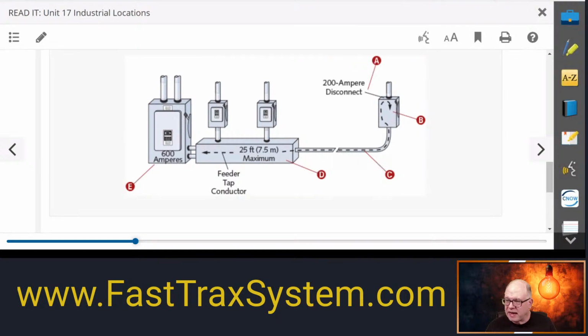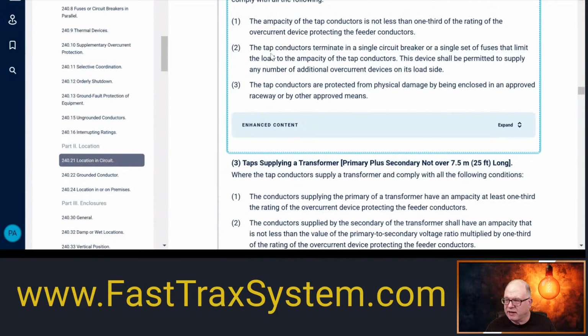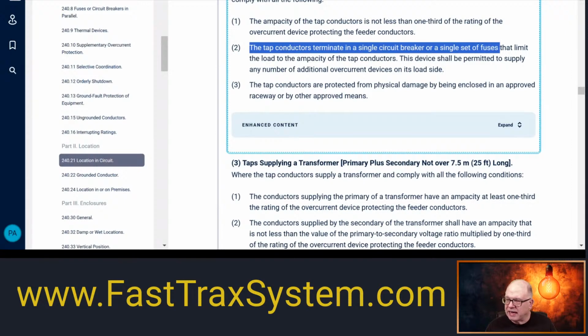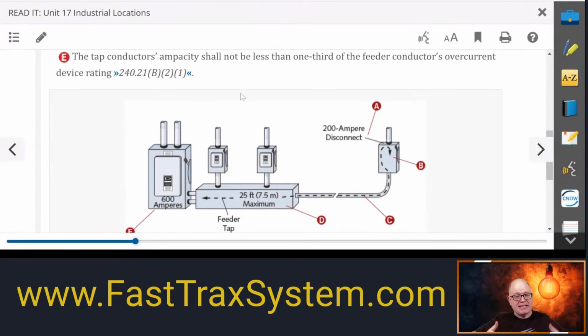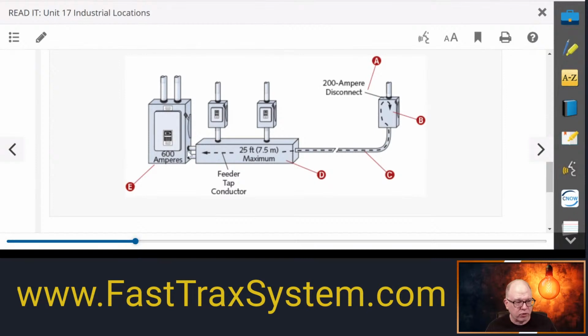Second caveat: the tap conductor terminates into a single circuit breaker or single set of fuses that limit the load to the ampacity of the tap conductor. Well, that's pretty straightforward. So all this is being dictated for us. This is a 200 amp because of the first rule we looked at. And since it's going into a 200 amp overcurrent device, this device is limiting the load to 200 amps, which is the rating of the conductor. So it's all working out. It's terminating into a disconnect, which maybe is a single main breaker or whatever it is, and then maybe it's feeding a panel board on the load side, rated 200 amps. Everything looks good so far.